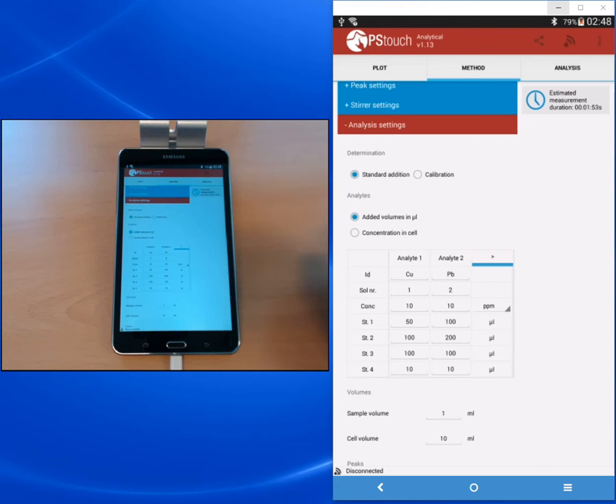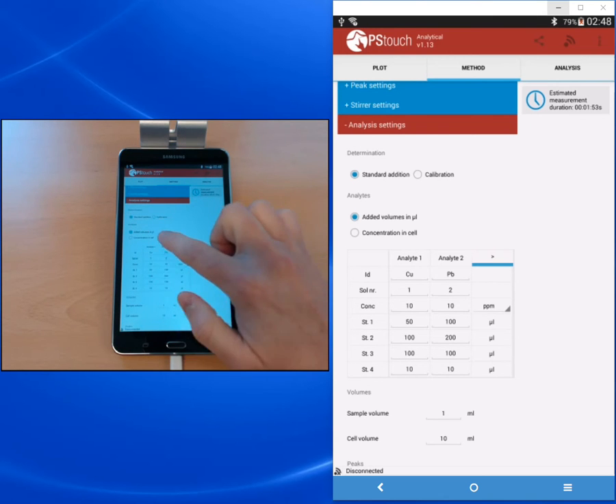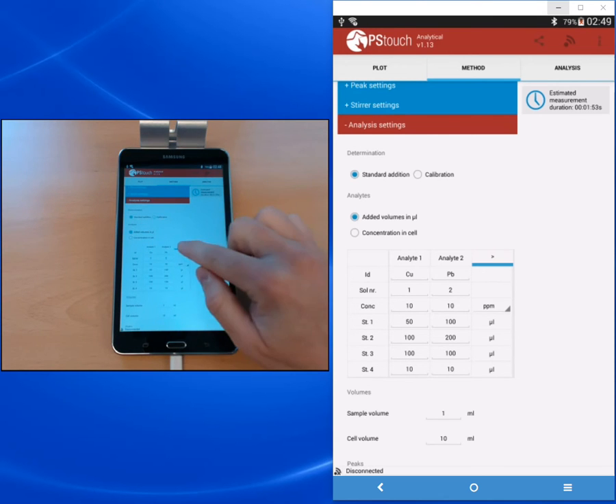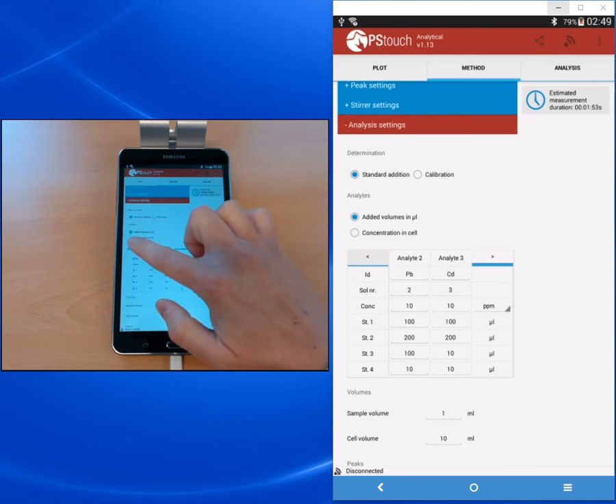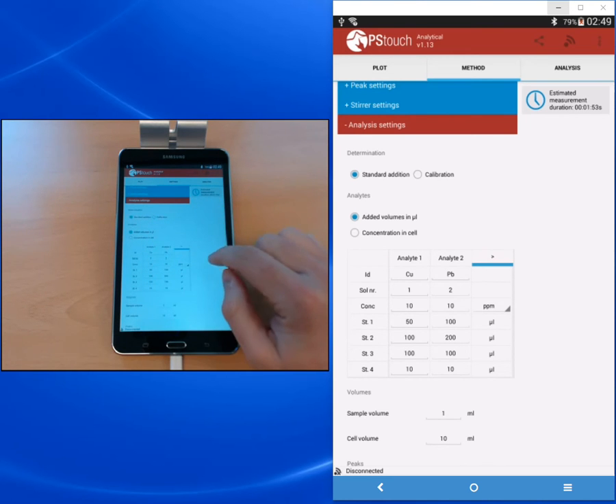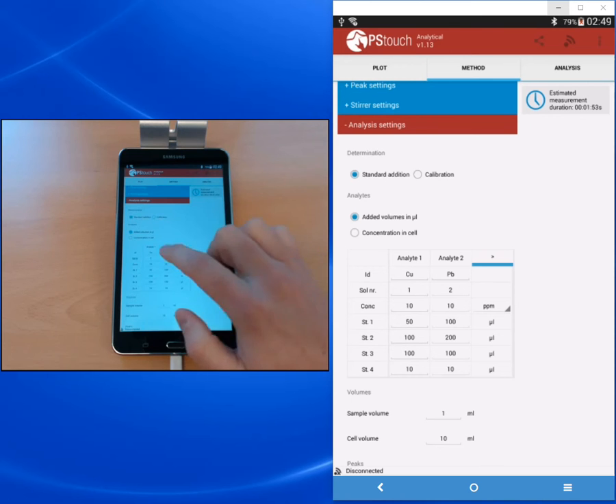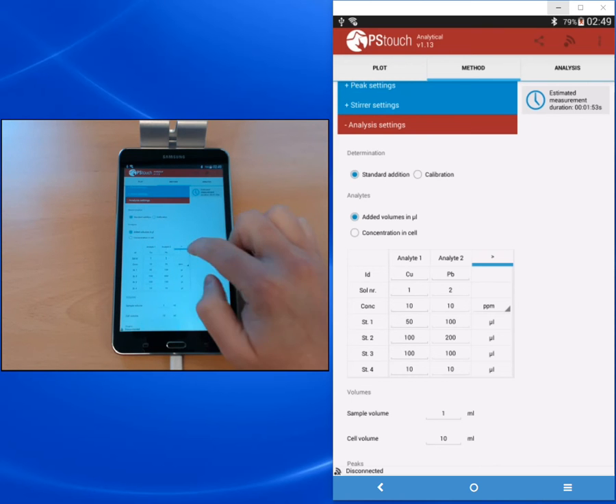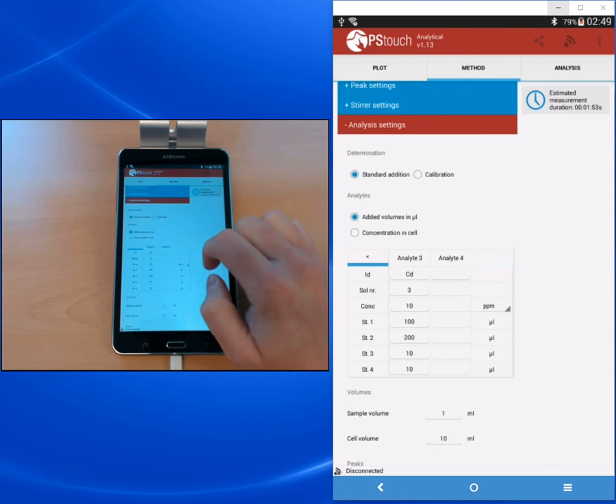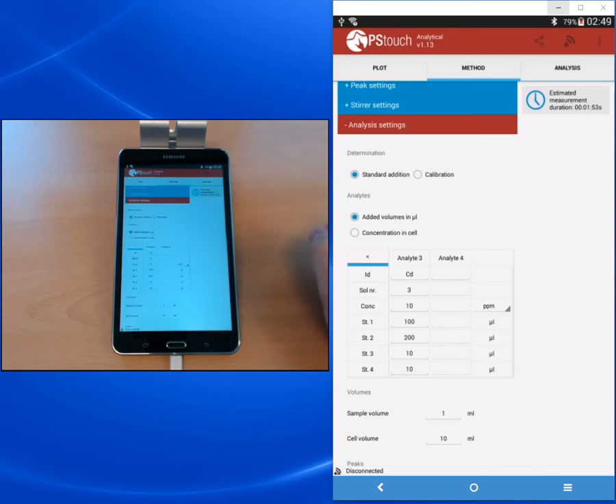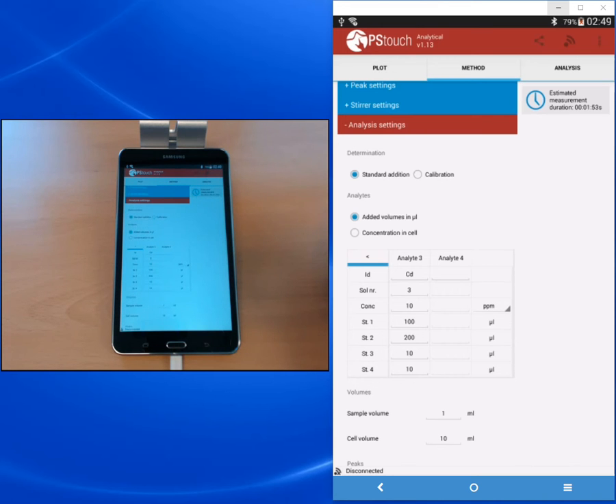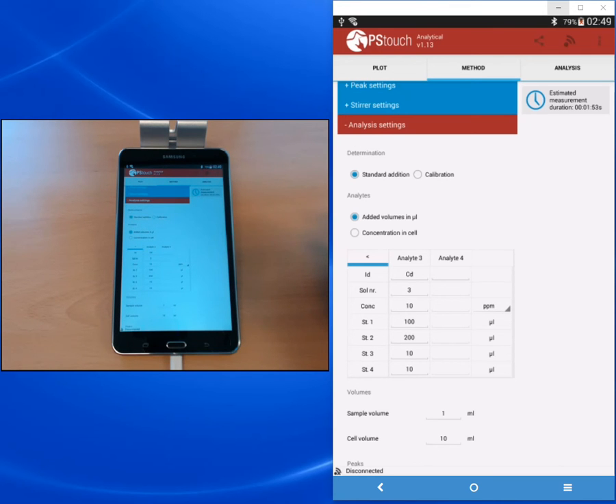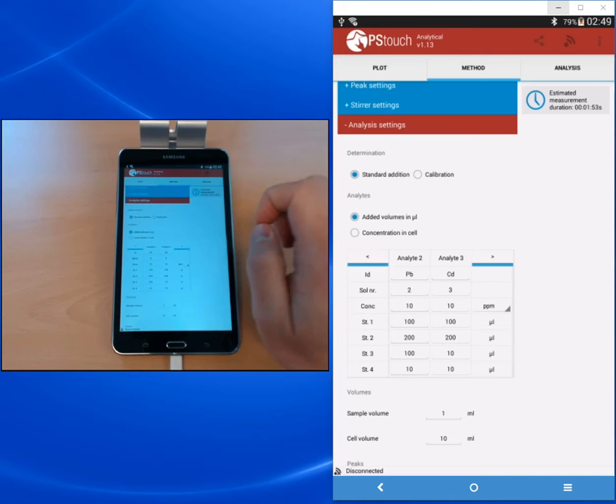We are going to look at the added volume table. In the table you see that every analyte has its own column. You can scroll through the columns for up to four analytes using the arrows on the top left and top right. Then we have the ID row. In the ID row you enter the name that you want to be associated with your analyte. This can be something like DDT if you are looking for organic toxins. This sample is river water and we are looking for heavy metals, so we just took the symbols from the periodic table. What you enter in the ID row will be used for the labels of the peaks.